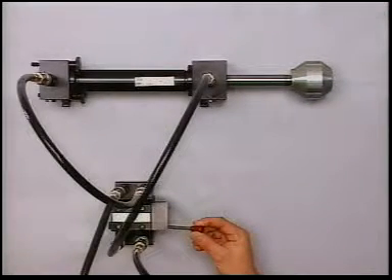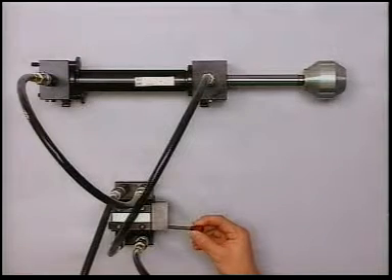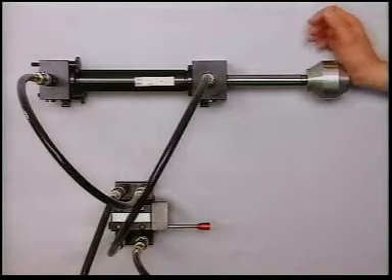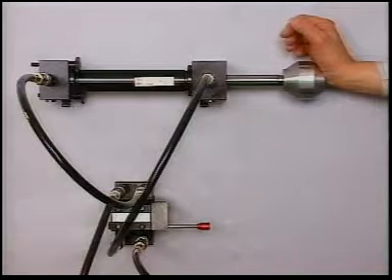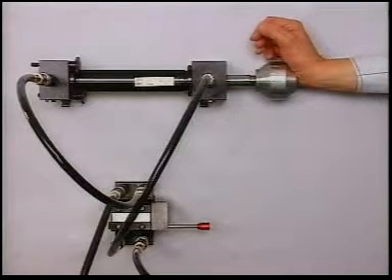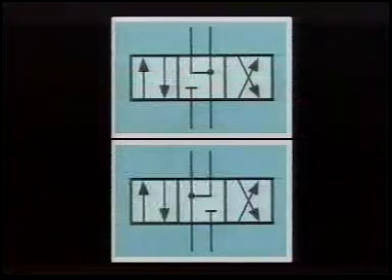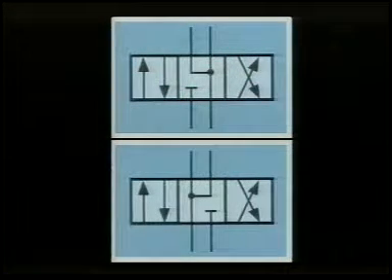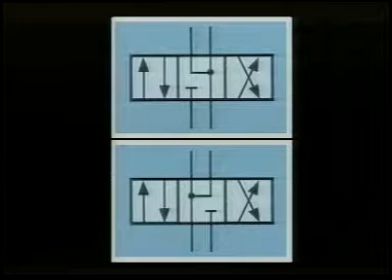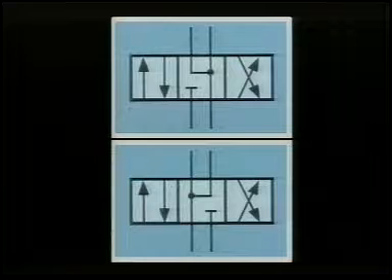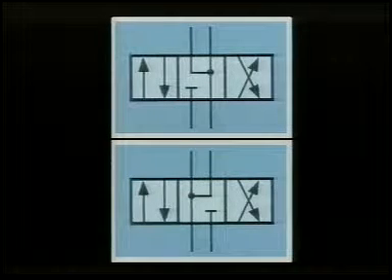Negative piston overlap like this is needed, for example, when the piston of a double-acting cylinder is to be moved by an external force. This only works because the left and right-hand chambers of the piston are almost completely unpressurized. We can also have positive and negative piston overlap within one multi-position valve. The combination used is determined by the application.